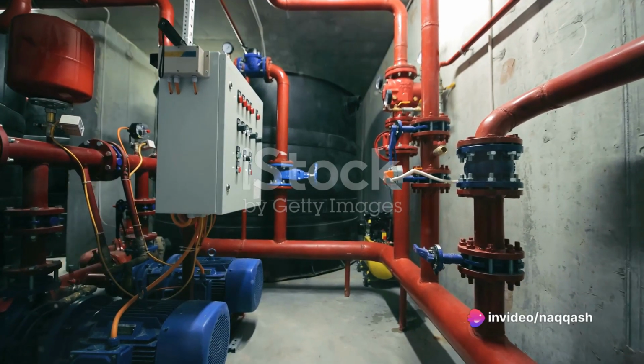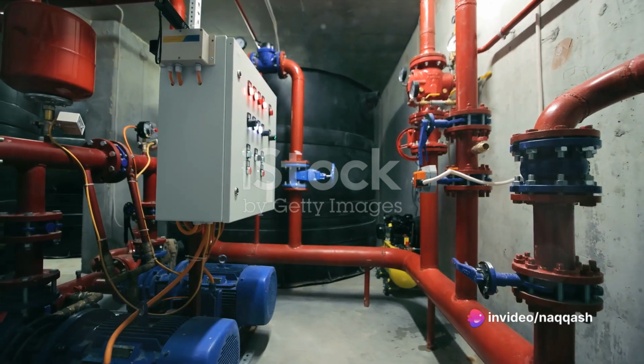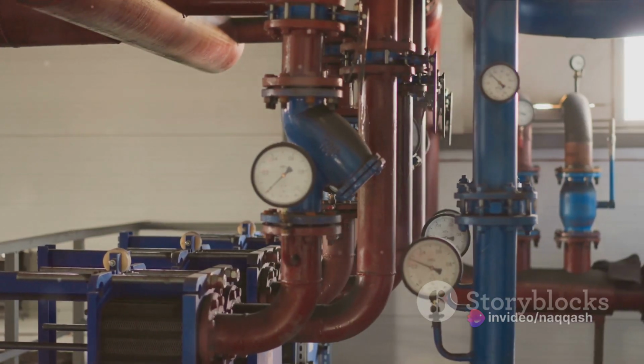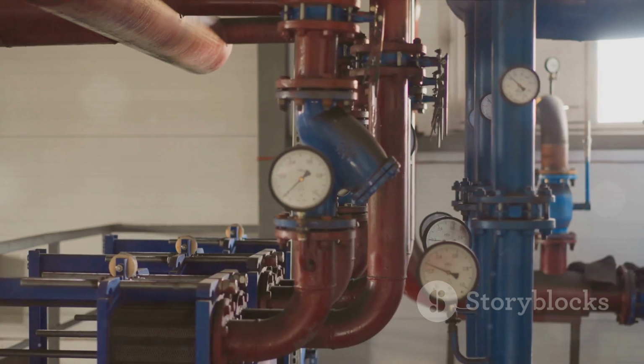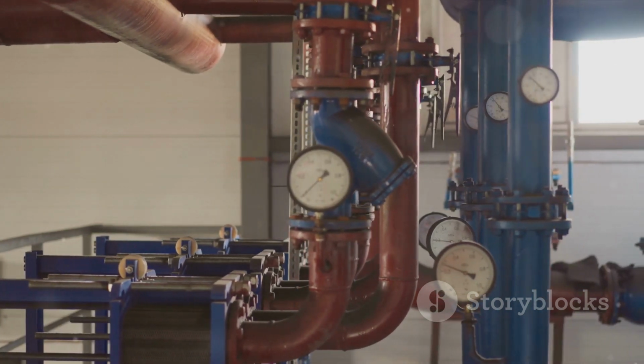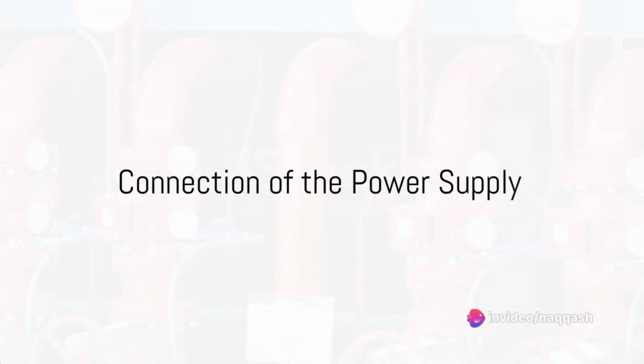This device is responsible for starting the pump when a fire is detected. It should be located close to the pump, but not in a location where it could be exposed to water or excessive heat. Following this, the pump's power supply should be connected.